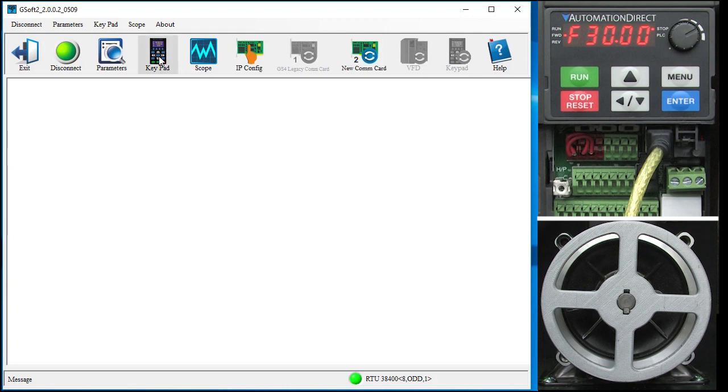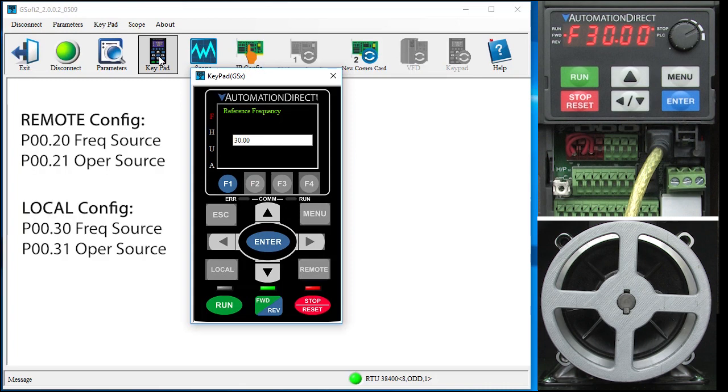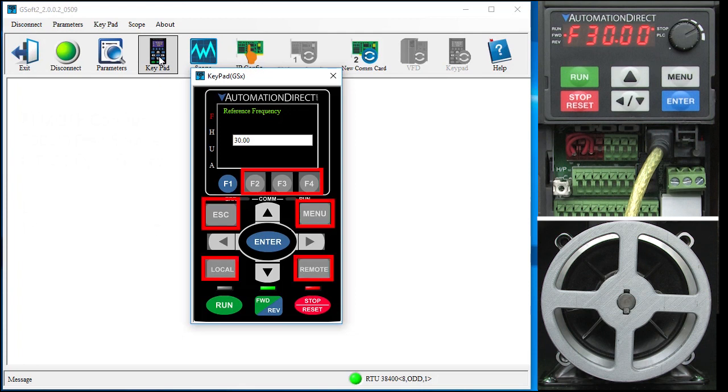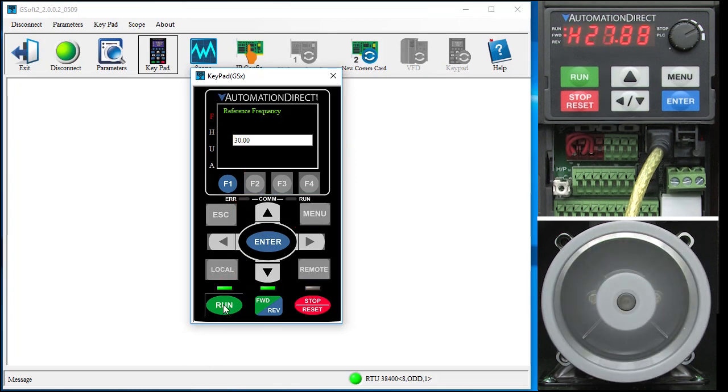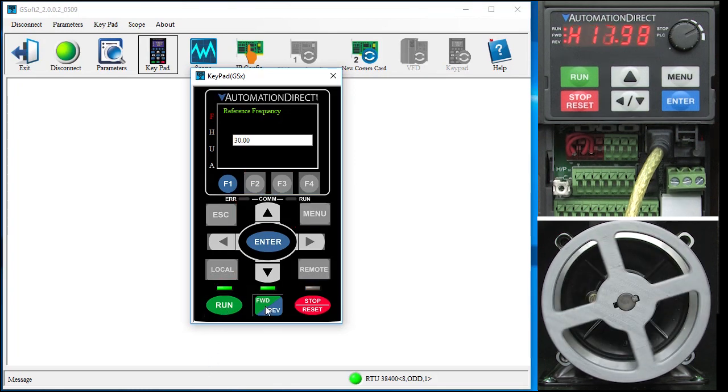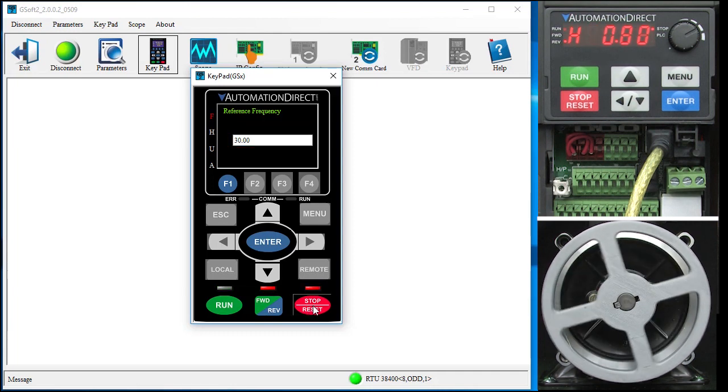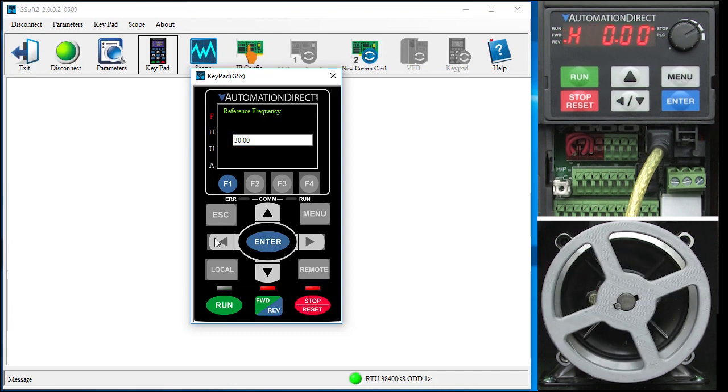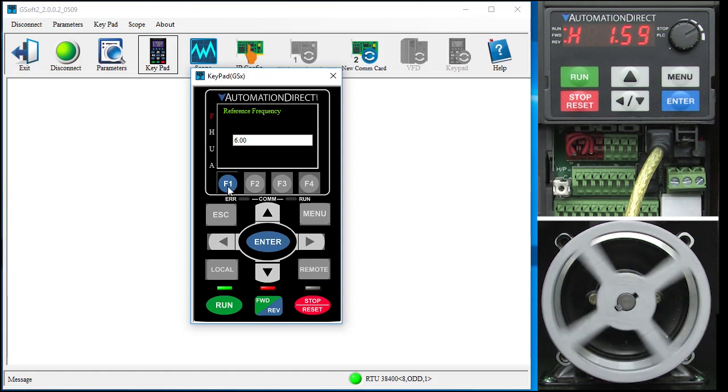This is a virtual keypad. It is like using the optional GS4 keypad, which we have a separate video on, so you have to make sure that the local or remote configurations are set to use the RS-485 as their source for frequency and operation. The grayed out buttons aren't active, but you can run, change direction and stop the drive and change the frequency. You can also jog the drive by clicking here. You have to hit the stop button to stop jogging.